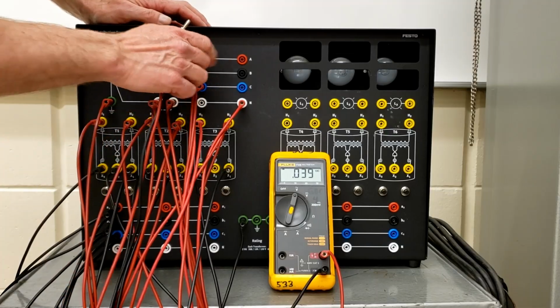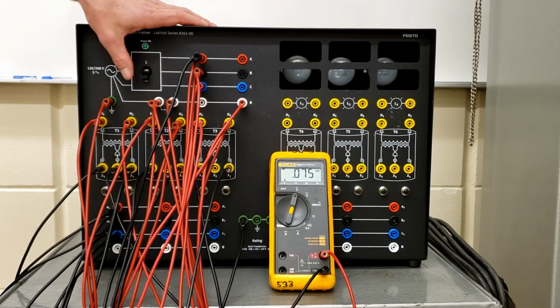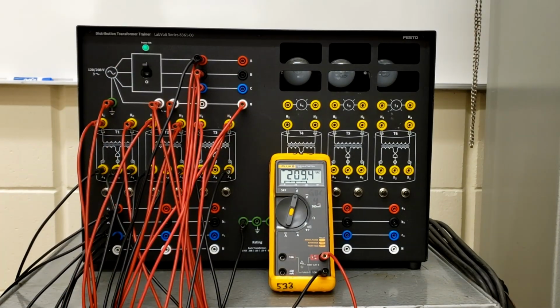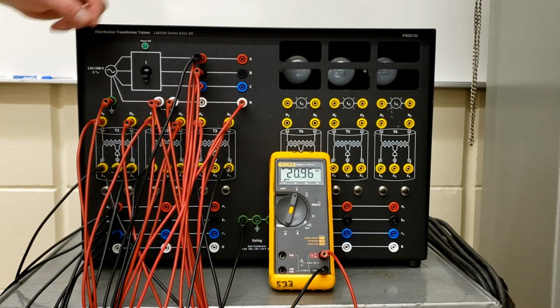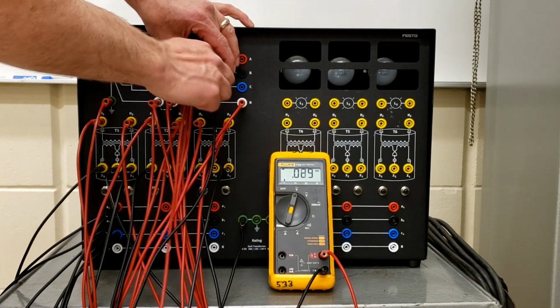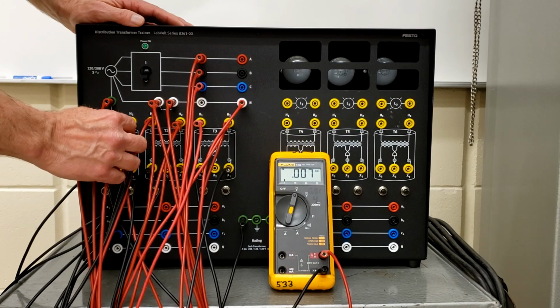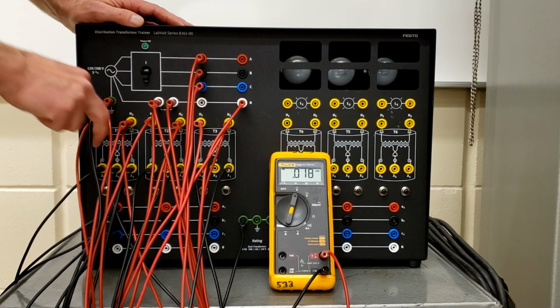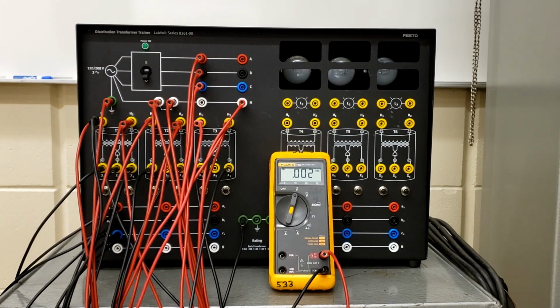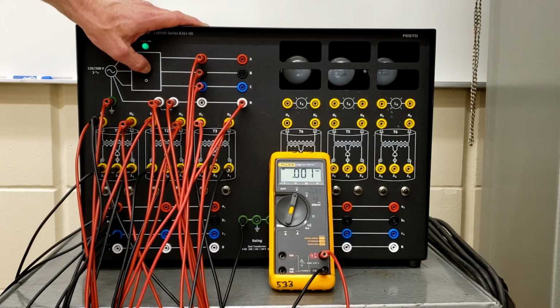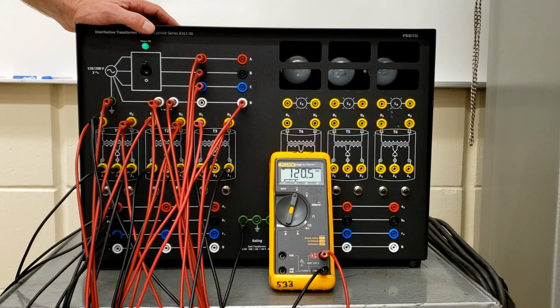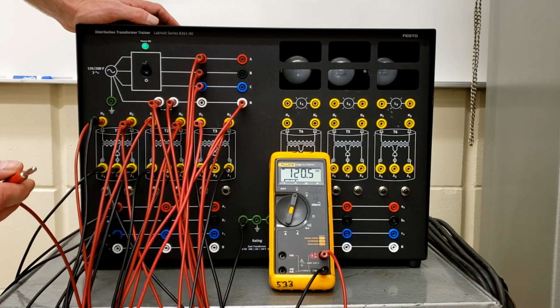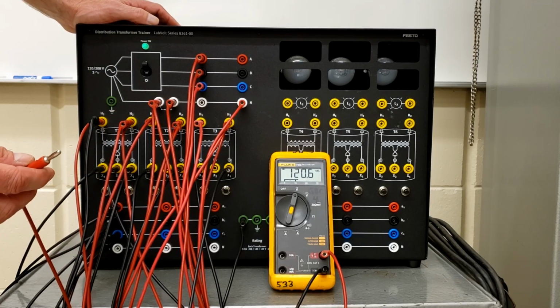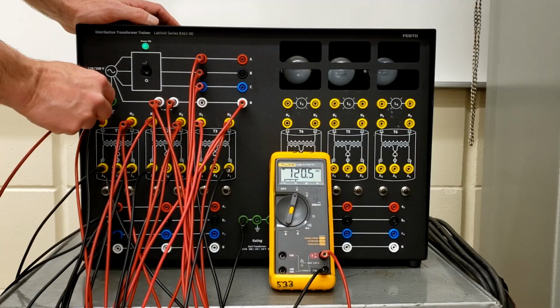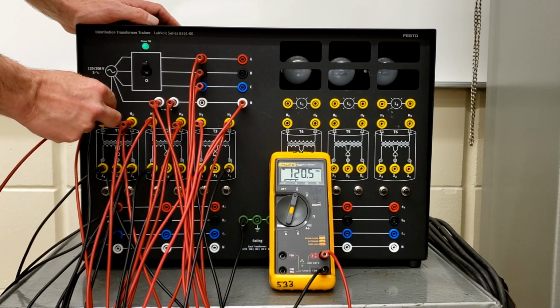Obviously, we've looked at this so many times, but this is going to be 208. Okay, looks good. It's 209 today. And let's look at the voltage on the primary windings here. So we're going to go from H1 to H2. Now that is a Y, so that should be 120 on the phase there. Beautiful, so there's 120. If we lift this ground, does it change anything? No, it doesn't change anything whatsoever. Okay, so not sure if that's required there or not. I'm going to have to check.